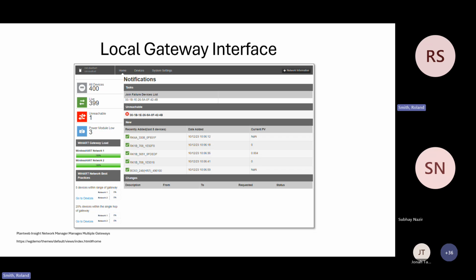On the left-hand side you see a quick snapshot of how many devices should be on the network. This one's typically saying 400 should be there, with 399 live, so 1 is unreachable for whatever reason. It may have fallen in a pond, somebody stole it, or the power module may be totally dead, requiring further investigation. One nice option is it also tells you of any devices with power module voltage drop to a certain level, enabling you to change out that power module before it drops off the network and becomes an issue.